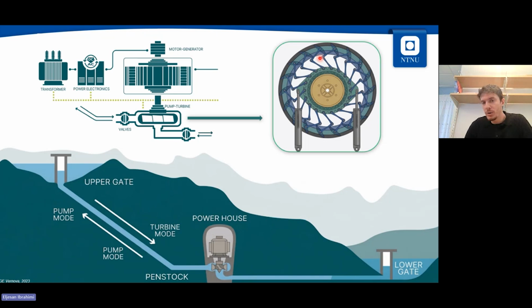Okay, so what about pumping mode? Well, this is simply not possible in the pumping mode because the turbine is driving the water, and if we try to restrict the flow of the water, then we move the turbine into an unstable mode, and we can damage the turbine. So this is the biggest issue, and how converters come into play here is by allowing the turbine and the generator to spin at a different speed by decoupling the generator from the grid.